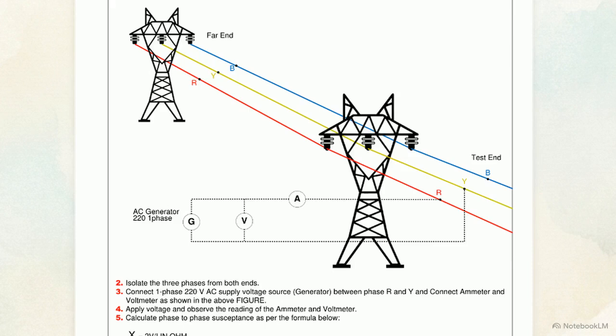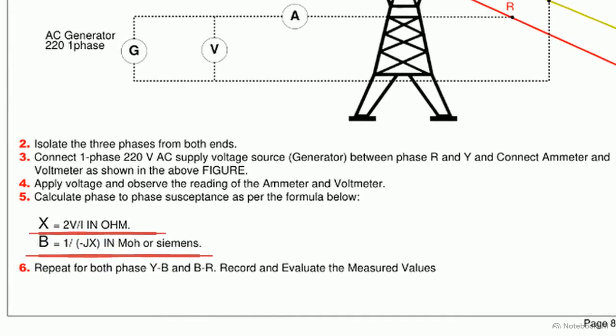Test 13.5 measures transmission line susceptance. A single-phase 220-volt AC source connects across phase pairs, starting with RY, to record voltage, current, and frequency. Using these readings, calculate reactance with X equals 2V over I, and susceptance using B equals 1 over negative JX. Repeating this for all pairs proves if capacitive susceptance is balanced and aligns with design data.